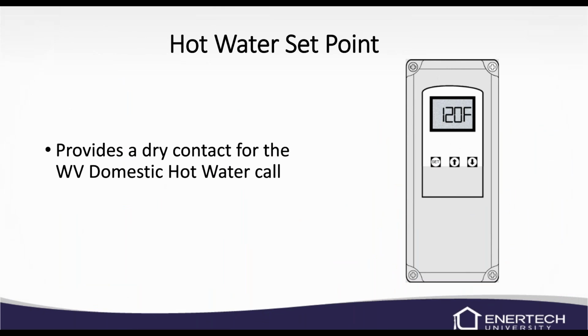So those are the controls. Another control that we have is an aquastat for your domestic hot water. And so basically it just provides the dry contact for that. You can set that. A lot of times I see them 120, 125, somewhere around there, with about a 5-degree differential or so.